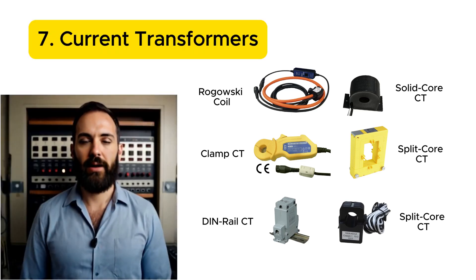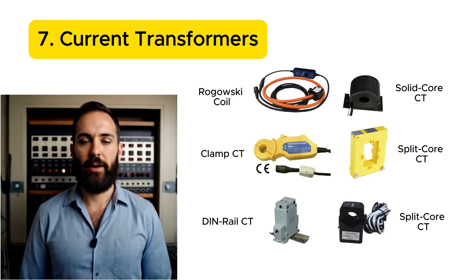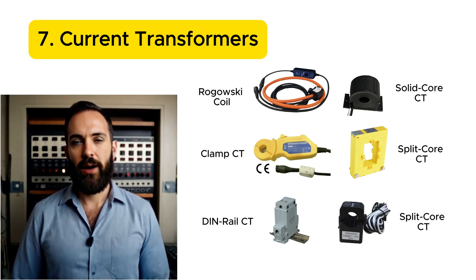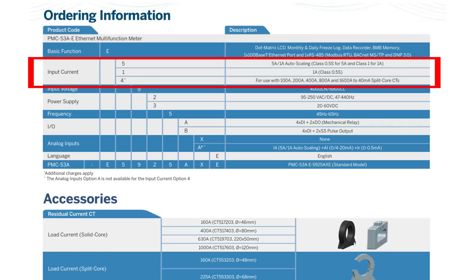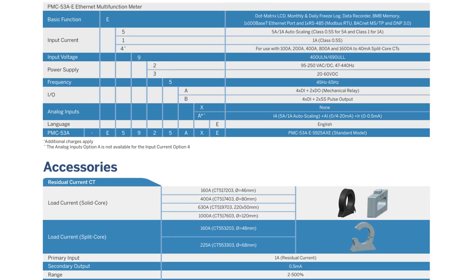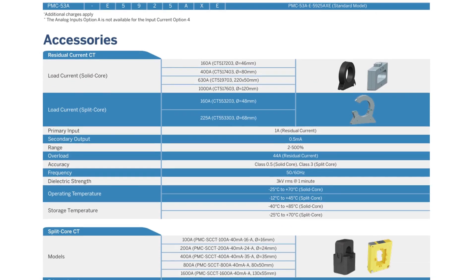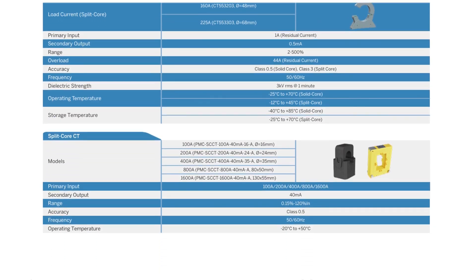Number seven: current transformers. The most common types of CT used for digital meters include split core CT, solid core CT, Rogowski coil, and DIN rail CT. They normally come in one amp or five amp ratings in the market, but beware that some CT are lower than one amp. So when ordering a meter, make sure to check the input current specifications and select the proper CT that works with the model.